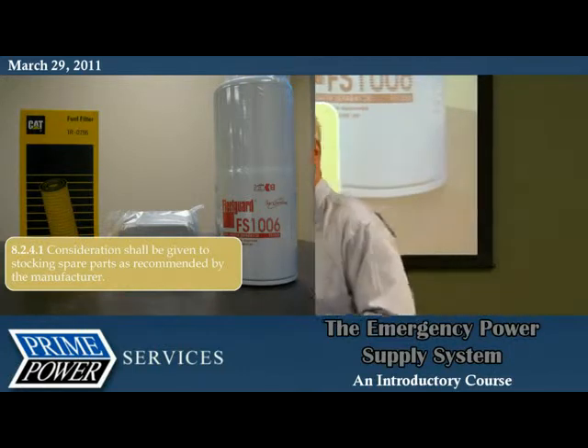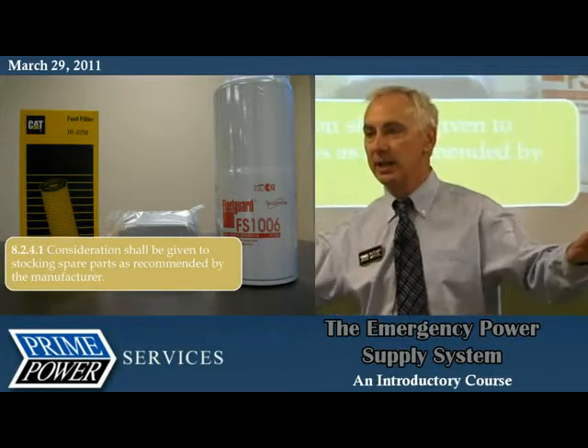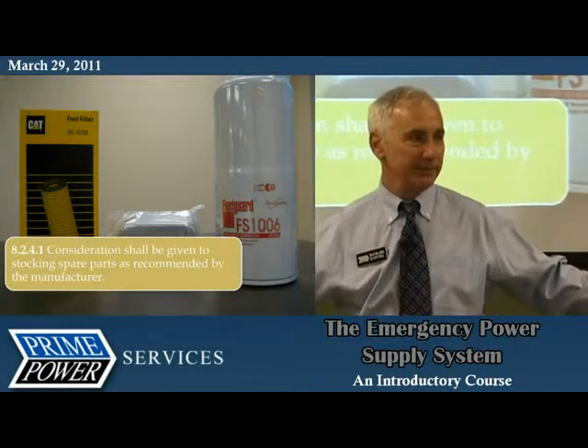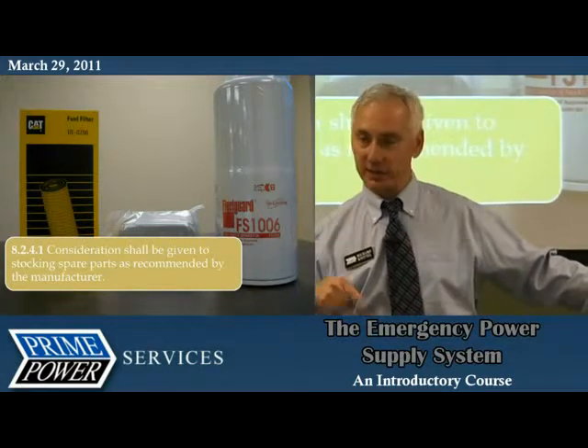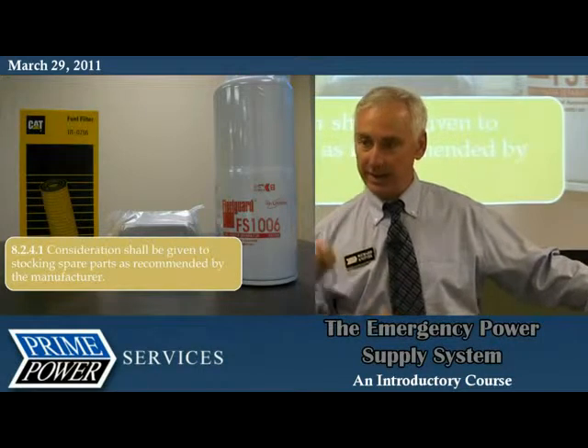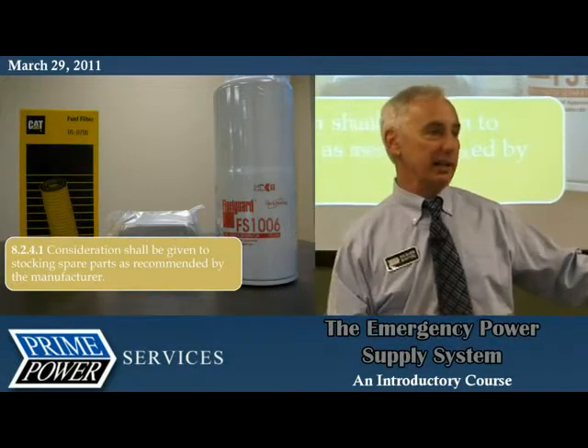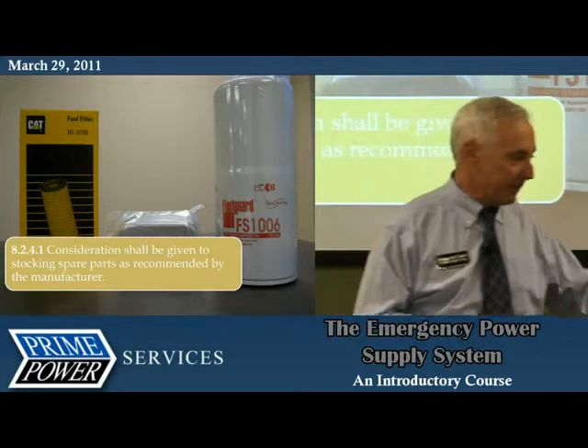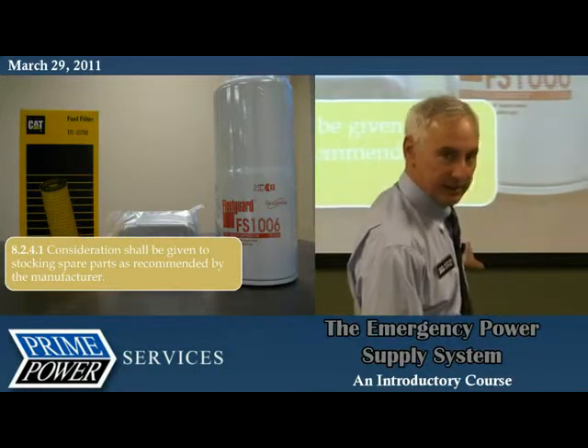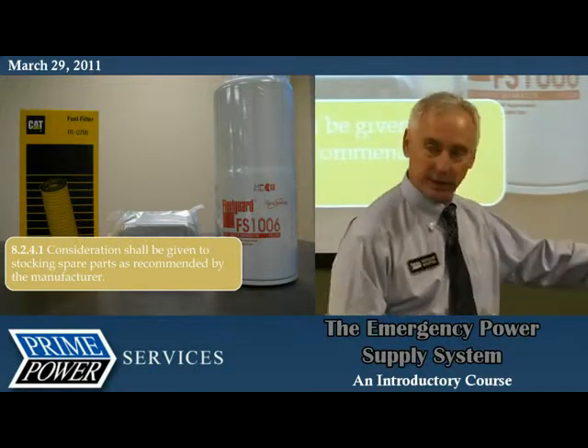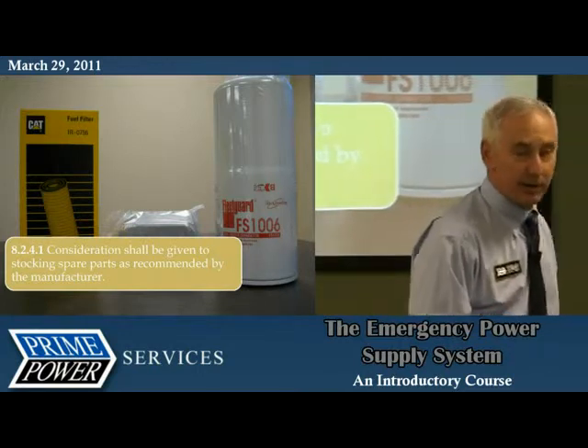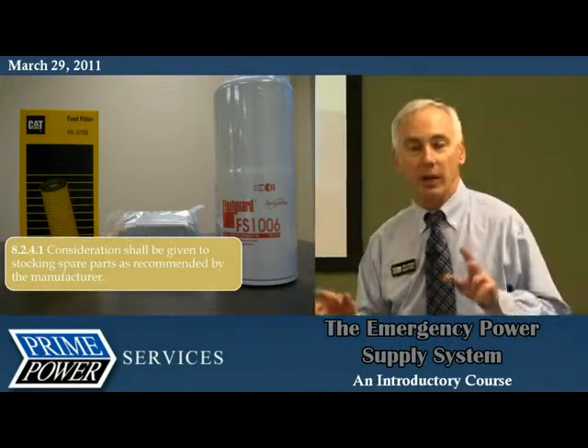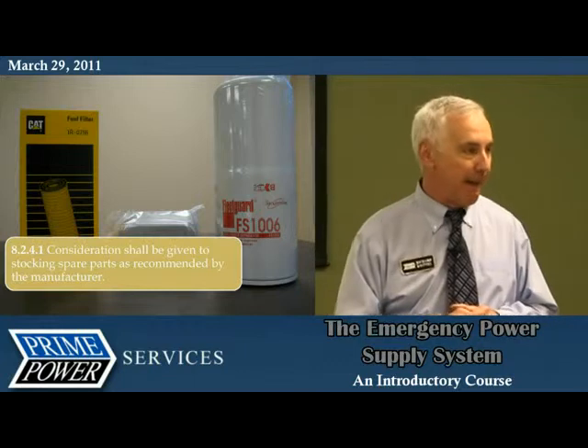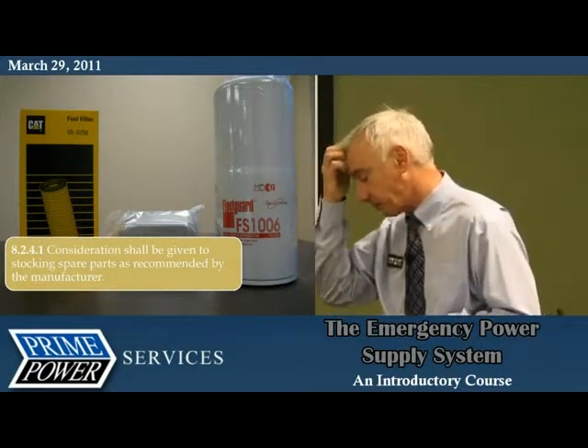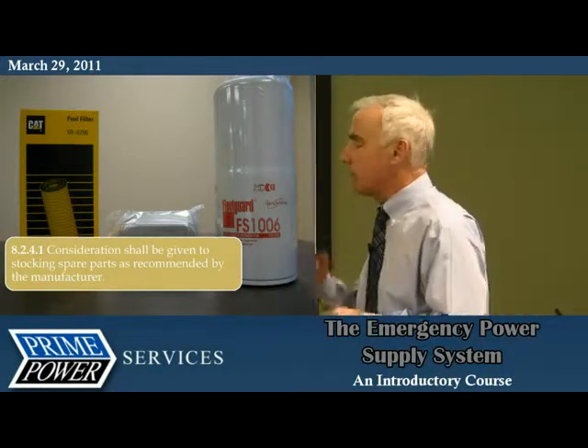This fuel tank that's been sitting there nice and calm and settled, nothing's wrong with it, until he puts a 2-inch pipe in there and stirs up every bit of grit on the bottom of that tank. And you're running until that grit hits this fuel filter, and now you're not running. So depending on what's going on out there, you've just shut down and you can't do anything about it. So we do recommend the fuel filters.